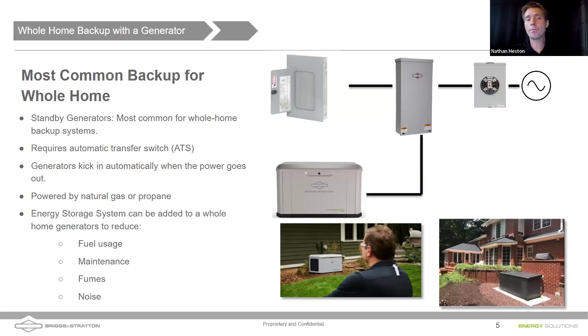Yeah, and Daniel, one thing you didn't mention is that this transfer switch shown on the screen has the ability to do some load shedding as well, giving you control over what loads are coming on. So you could—we're showing a 26K PowerProtect there—but you could actually back up your whole home with a smaller generator if you're careful not to overload it.